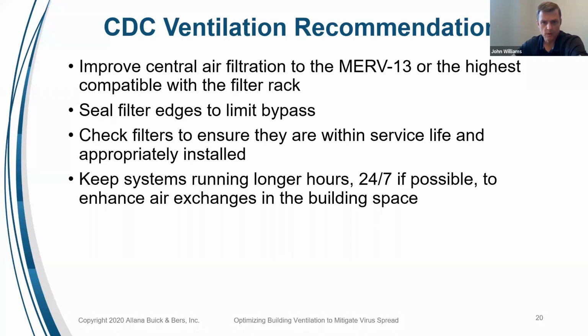Okay, let me see where we're going. The next thing I had in here was we want to make sure we're changing the filters. So in addition to making sure that the filters fit and there's no bypass of the air, we want to make sure we're keeping up with our filter changes. Typically on a return air unit, that is about every 3 months or once a quarter. And typically on outside air units, it's monthly if it's a 100% outside air unit. But again, that's going to vary depending on your geographic location and the system use and what the system serves. So filters must be changed. And again, there's no one size fits all.